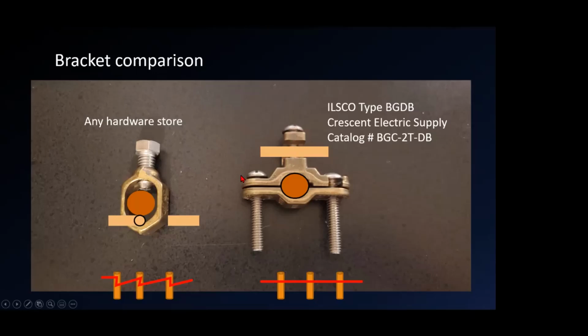Which also means you don't have to go to the hassle of threading 9 connectors like this onto 95 feet of copper wire, because there's no way to get it in there unless you do that. So this is my recommendation if you're going to go with just a straight mechanical clamp like I did.